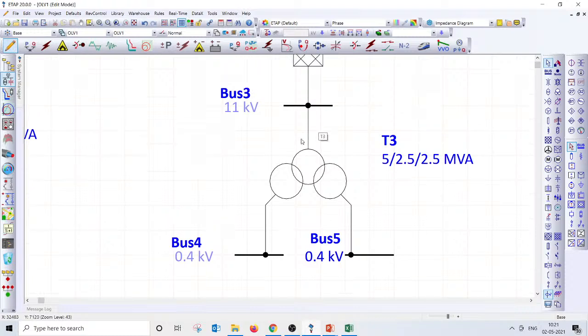Right, so that's good. So if you want to go for higher ratings, and if your reliability requirement is not so severe, then you can think of a three winding transformer. And for plants like solar plants, where the plant load factor is just about 20%, it is quite common to go with four winding and five winding transformers. That means if you take that transformer for maintenance, you will be completely losing all the four inverters which are connected, and you will be losing the power generation from that, but it still saves quite a lot of cost on the MV switchgears, so the capital investment is worth it. Thank you Praveen for saying that that transformer is there at your site. That's great.